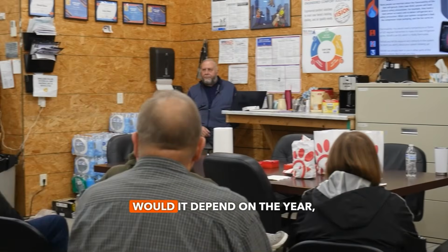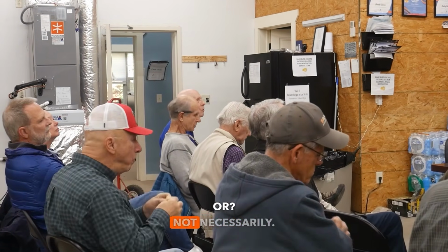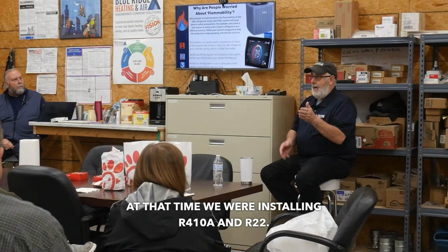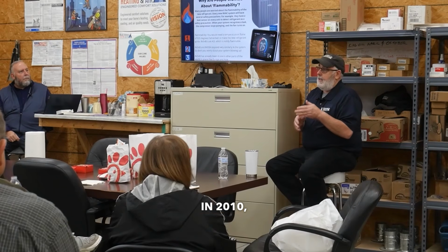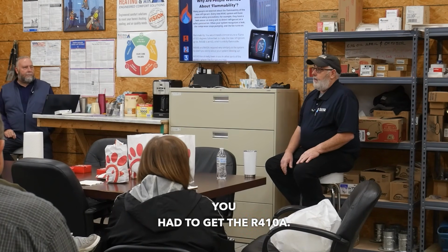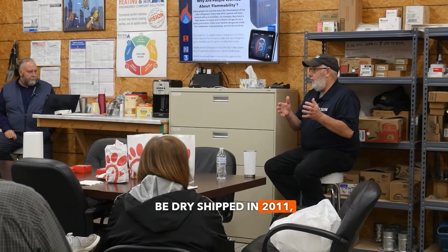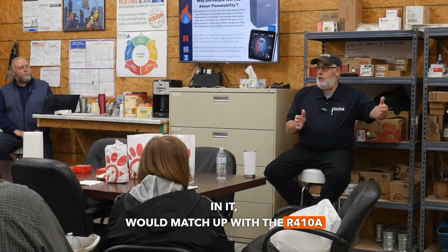Would it depend on the year, the vintage of it, and make, or not necessarily? In 1996, they started coming out with the 410A, and at that time, we were installing 410A and R22. R22 was the old refrigerant that was phased out. In 2010, they stopped manufacturing the R22 systems, and you had to buy the 410A systems. Now, some of the systems would be dry shipped in 2011, 12, 13, where they had no refrigerant in them, to match up with the R22 systems.